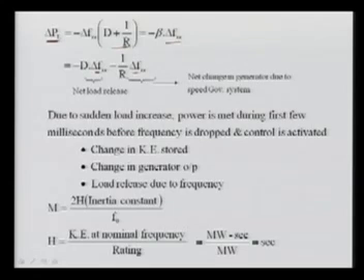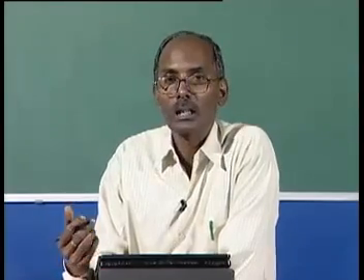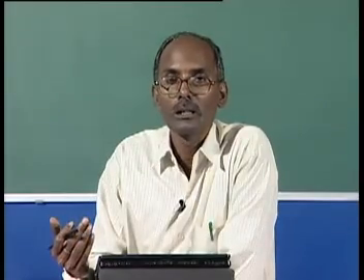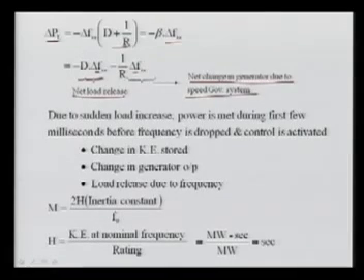This component is called the net load release, and this component is called the net change in the generation due to the speed governing system. Means when frequency falls, as we saw in the characteristic of the speed governing system, the governing system will try to increase the input so that frequency can be increased and maintained. So this is due to the governor characteristic, and R is the characteristic that we have explained here. This is your loading and this is your change in the frequency. So the characteristic here is the drooping characteristic.